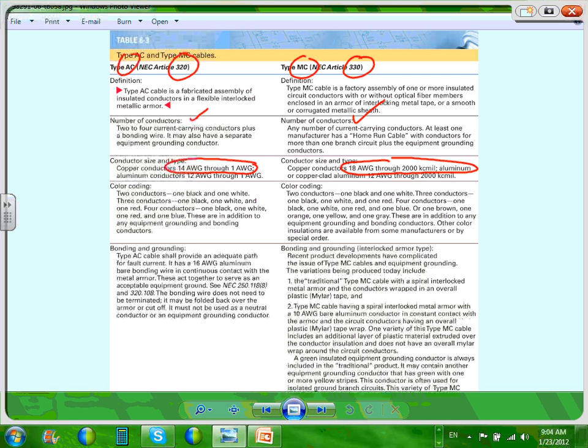If you are, later on, guys, if you're using a cable tray, and you don't want to use conduits, you want to bring cables in a cable tray, MC cable becomes a very good option. You can use a multi-conductor MC cable where you can bring 500 kcm, 4 conductors, 500 in a cable, sit it on that cable tray and shoot it all the way to the other end versus what? Putting it in a conduit and THHN. So it becomes a really very major option, MC cable.